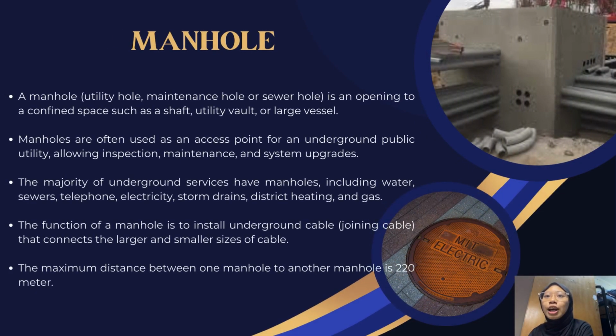A manhole, utility hole, maintenance hole, or access hole is an opening to a confined space such as a shaft, utility vault, or large vessel. Manholes are often used as an access point for underground public utilities, allowing inspection, maintenance, and system upgrades. The majority of underground services have manholes, including water, sewers, telephone, electricity, storm drains, district heating, and gas. The function of the manhole is to install underground cable and join cable that connects larger and smaller sizes of cable. The maximum distance between one manhole and another manhole is 220 meters.